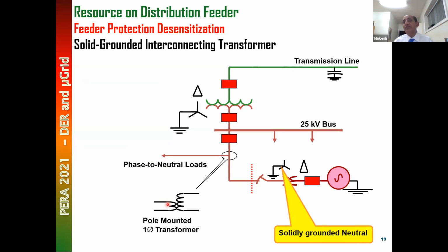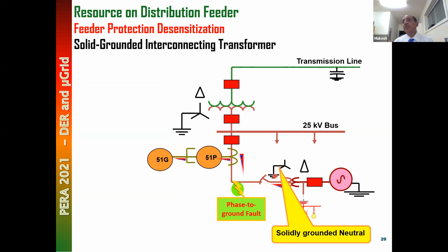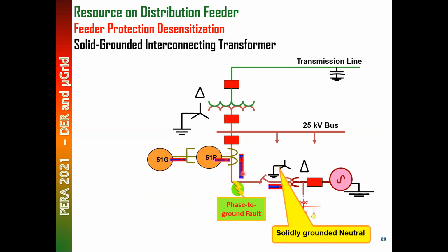So you would say, why not ground it? As I was saying, why don't we do grounding? Obviously, we can do solid grounding. Now if we do solid grounding, as I said, ground fault current will come from here, and ground fault current will come from here, and that will lead to desensitization of this ground protection.